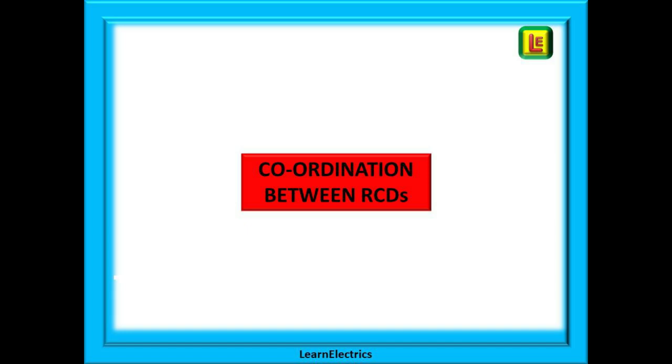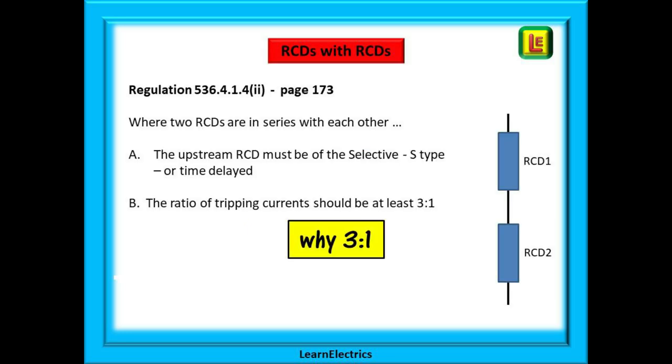We can look now at simple coordination between RCDs. Regulation 536.4.1.4 part 2 on page 173 of the wiring regulations tells us that where two RCDs are in series with each other then the upstream RCD must be of the selective S type or time delayed type and that the ratio of the tripping current of the two RCDs should be at least 3 to 1.